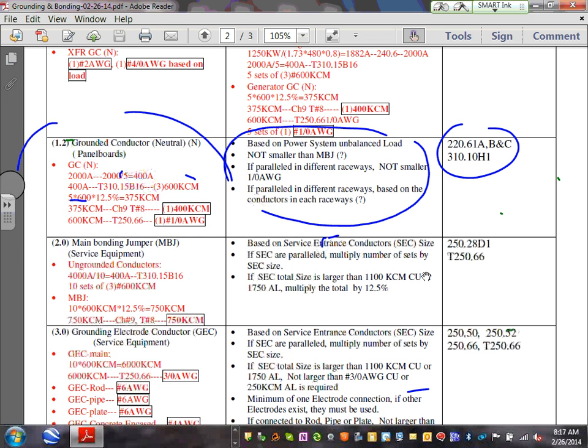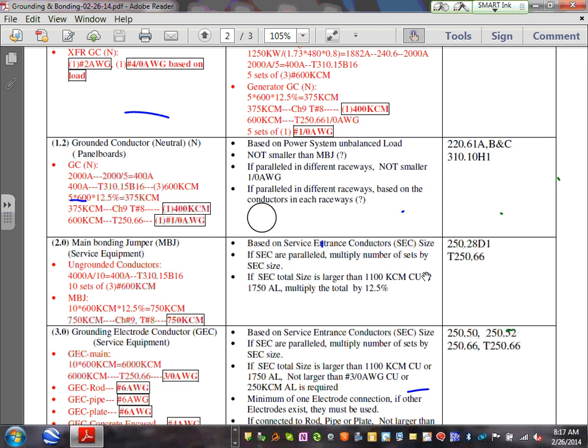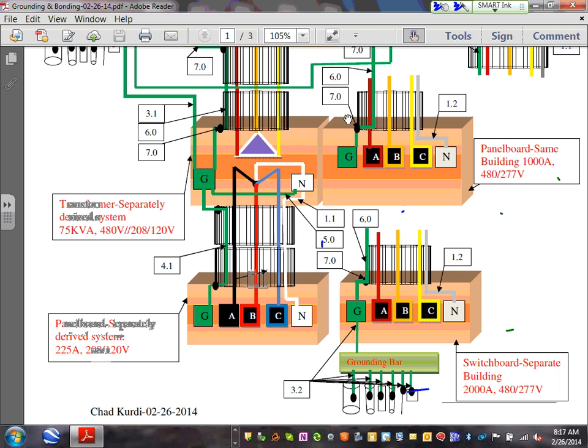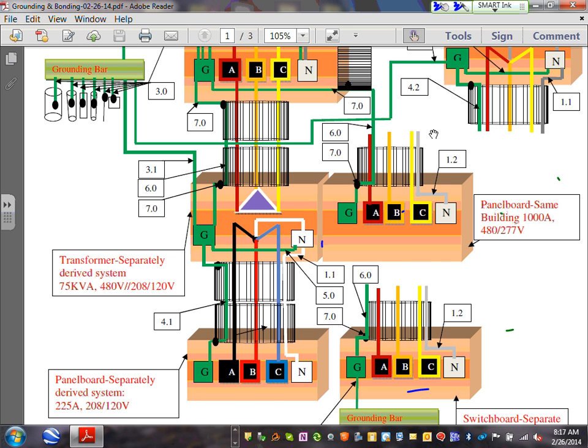Now let's go into number 6 and number 7. Can you guys see number 6 and number 7? Now, Adam, if your conduit is EMT conduit, your conduit will be your equipment grounding conductor. Did you guys hear me? If your conduit is an EMT conduit, your conduit will be your equipment grounding conductor. If it's rigid, it will be an equipment grounding conductor.